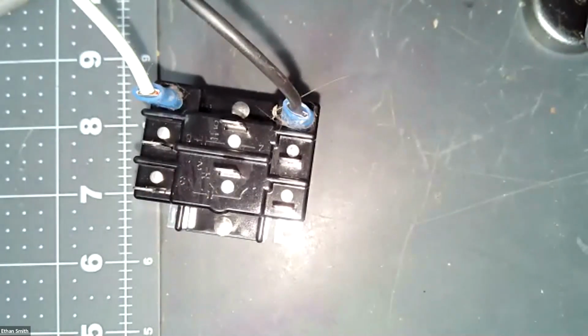So everybody knows how to diagnose a switch now, right? So when they're energized, we have what voltage drop across them? Well, if it's zero on the closed one. Yeah, when we've got an energized switch, it has 0 voltage drop across it. And when we have a de-energized switch, it's got whatever the voltage supplied drop across it. So closed switches, 0 voltage, open switches, source voltage. Any questions, guys? Okay. I know I was kind of crammed down in there on that meter.